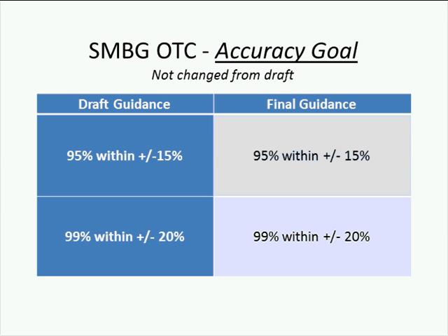The accuracy goals outlined in the SMBG guidance have not changed from the draft. And they stated that 95% of SMBG results in the accuracy study should be within 15% of the comparator method across the entire claimed measuring range of the device, and that 99% of the SMBG results should be within 20% of the comparator method.